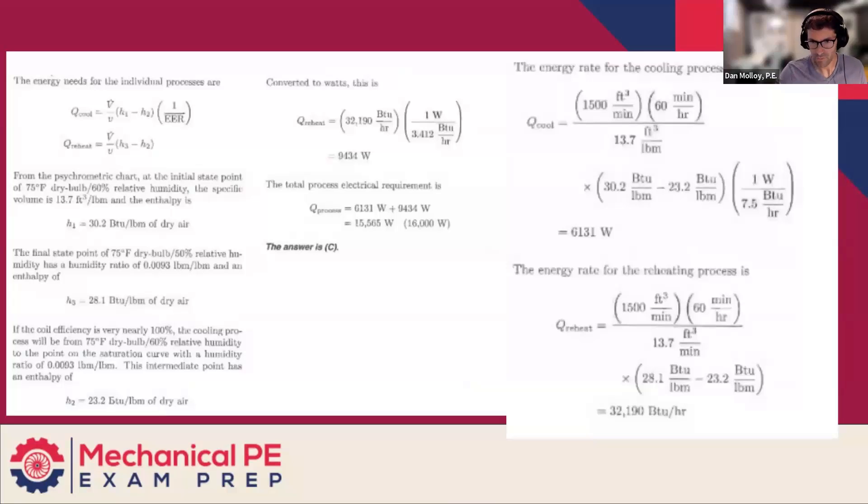And I think, yeah, if we look at the final answer, the 6131 was the compressor to do the cooling process. And the reheat was 9400. Like that's 10KW. That's a lot of juice. So yeah, we're working through it. We're going through on your own. And then the EER instead of the COP with being different units, you know, it's a minor thing, but if you haven't looked at EER in a while, you might kind of freeze up and go, what am I going to do with this? So just go slow and you'll be okay.